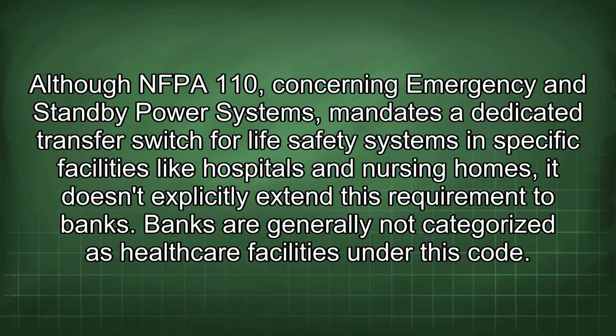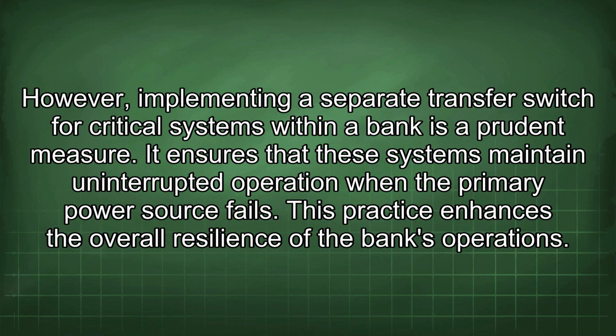Although NFPA 110 concerning emergency and standby power systems mandates a dedicated transfer switch for life safety systems in specific facilities like hospitals and nursing homes, it doesn't explicitly extend this requirement to banks. Banks are generally not categorized as healthcare facilities under this code. However, implementing a separate transfer switch for critical systems within a bank is a prudent measure. It ensures that these systems maintain uninterrupted operation when the primary power source fails. This practice enhances the overall resilience of the bank's operations.